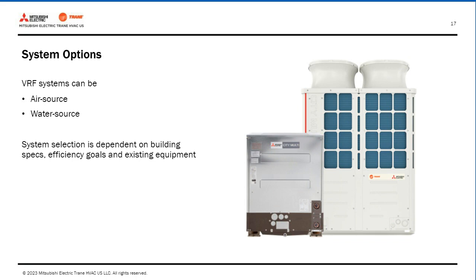Some of the benefit of the water source system is that the ground temperatures don't fluctuate like the outdoor air temperatures do. So that's why Credit Human, with the 300-foot deep underground wells, could store heat from the summer that the water source VRF could use to heat the building in the winter, which is also something that Matt will talk about, how that ground source system helped prevent major piping loss during the snowpocalypse, like Kimberly mentioned. Water source VRF systems can also provide the option of storing condensing units indoors, which we also see at Credit Human, and both options provide optimal energy efficiency and comfort.